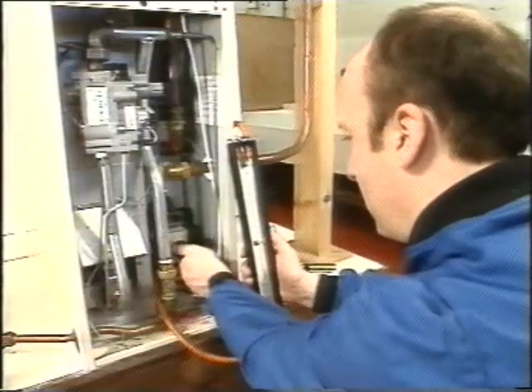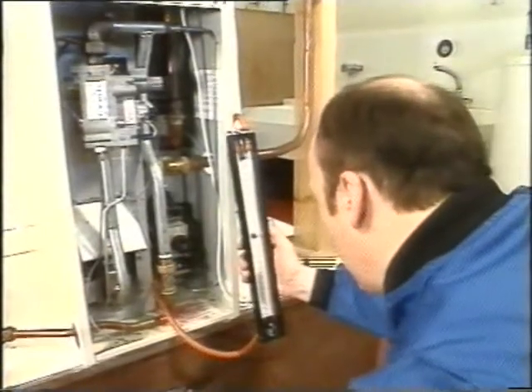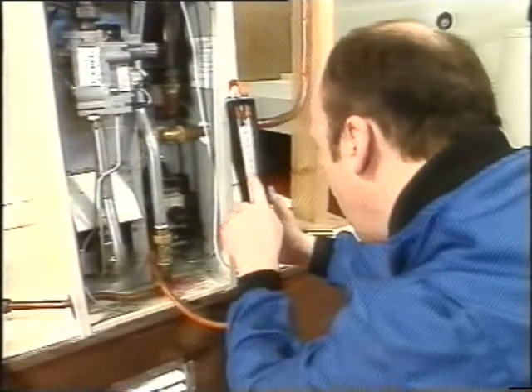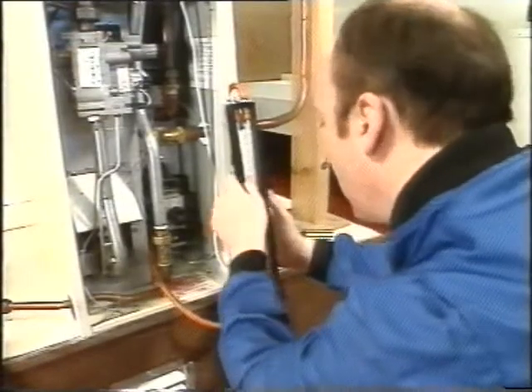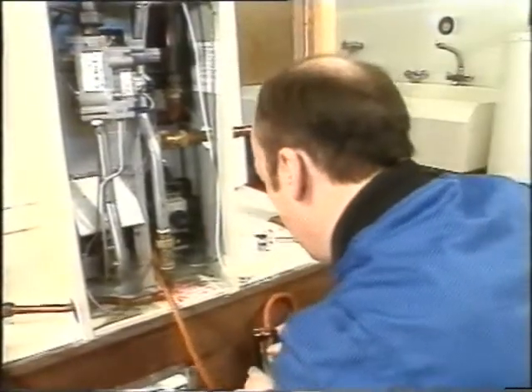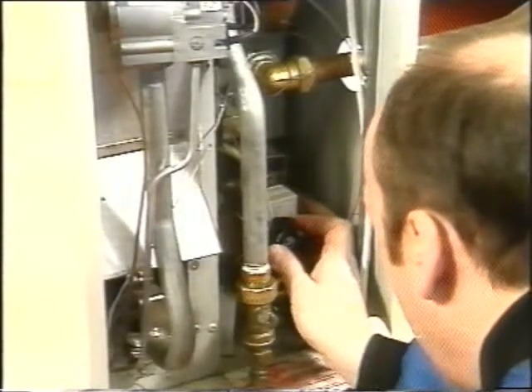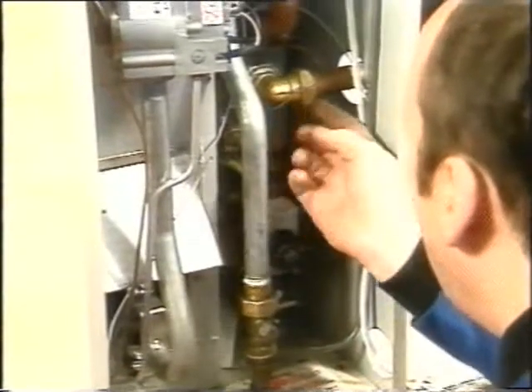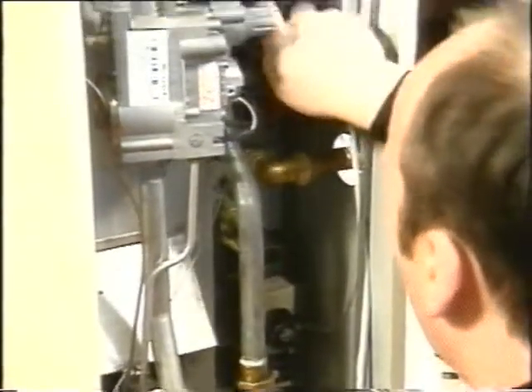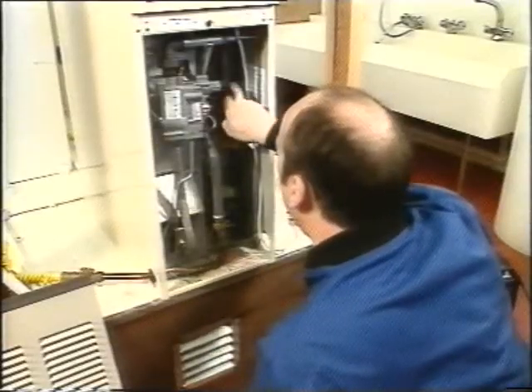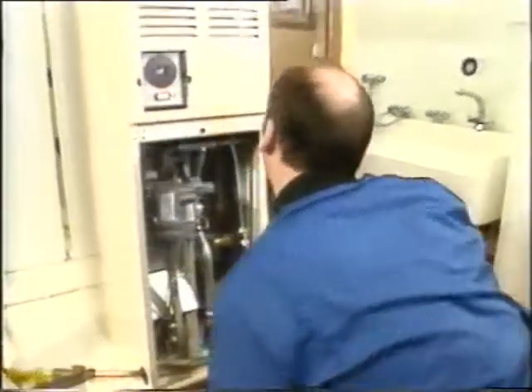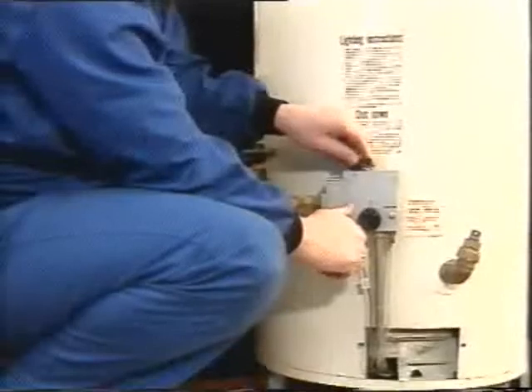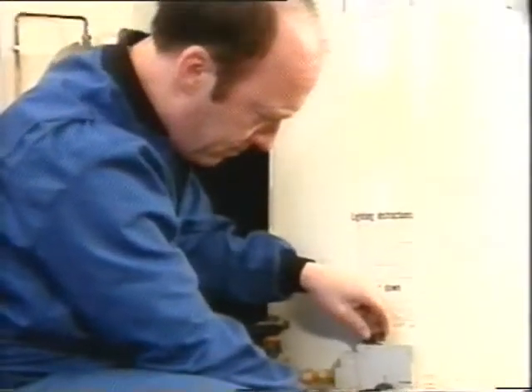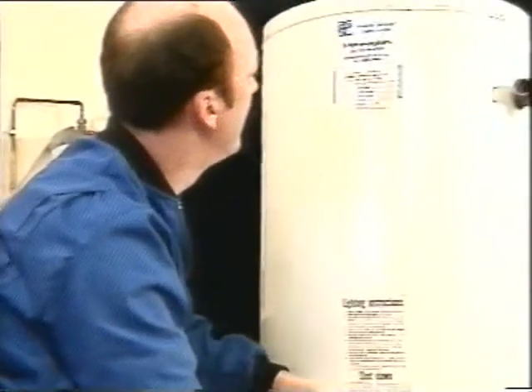If they're as they should be, move on to the burner. Test its pressure, the flame picture, and the gas rate. Finally, make sure the controls all work, that there's no spillage of flue products or water leaks, and switch it on to check that it's operating properly. And the final appliance for us to consider is this multi-point storage heater. It could be installed in place of a hot water cylinder.